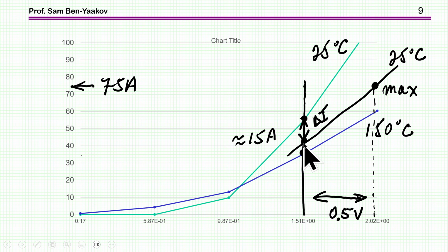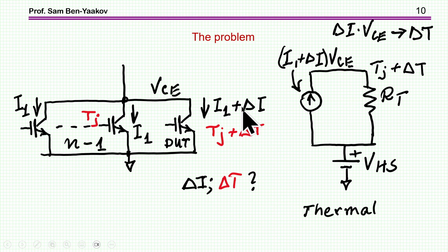So therefore, now the deviation between the typical and the maximum at this operating point, and this is a function of the operating point, it'll be different at another operating point. So if I walk here, meaning that the current that I'm talking about is 50, 60 amp, I see the deviation between the typical and the IGBT with this maximum value is 15 amp, okay? It's about 50.